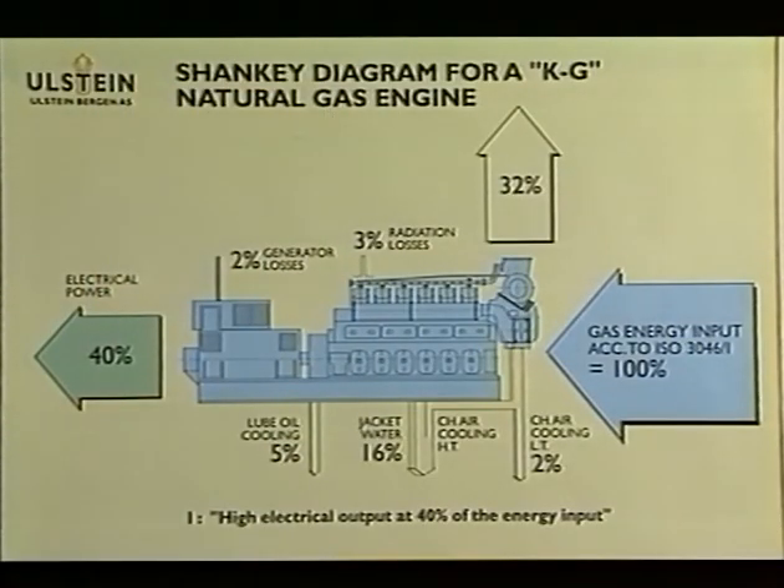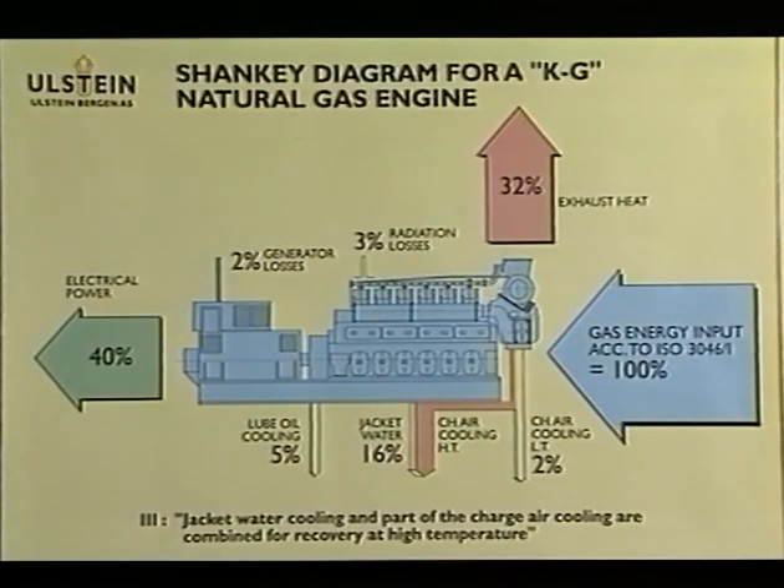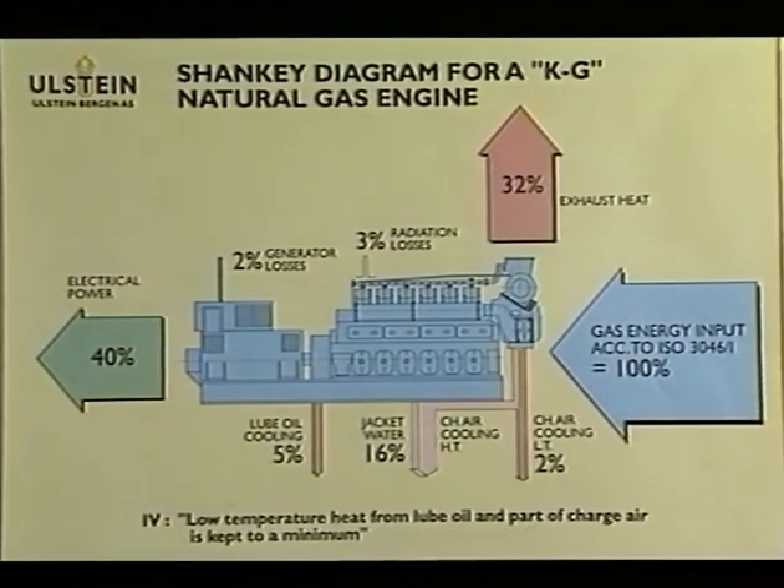The engine's Sankey diagram shows 40% for electric power, 32% for heat, 16% for jacket water and high-temperature charge air cooler, 5% for lube oil cooler, 2% for low-temperature charge air cooler, and 3% loss in radiation.